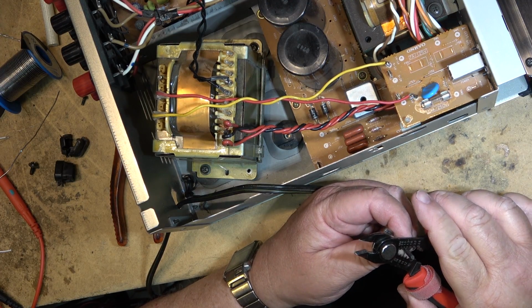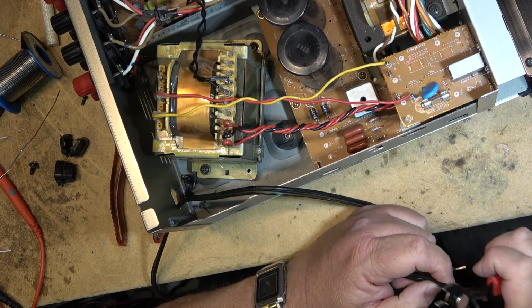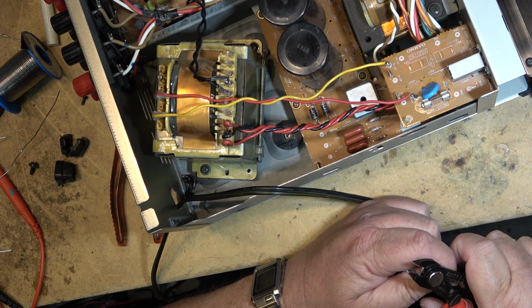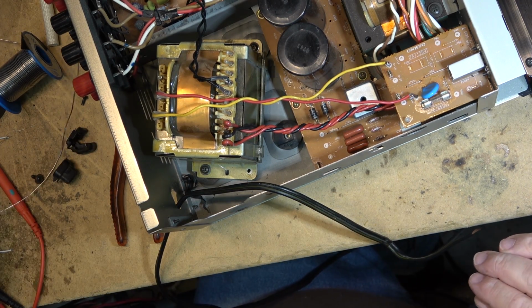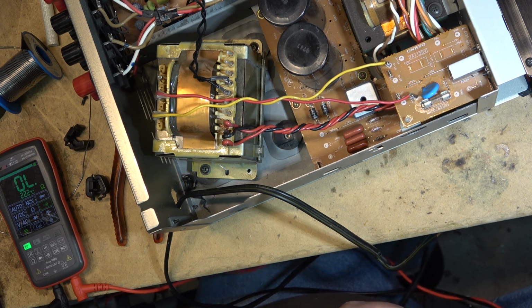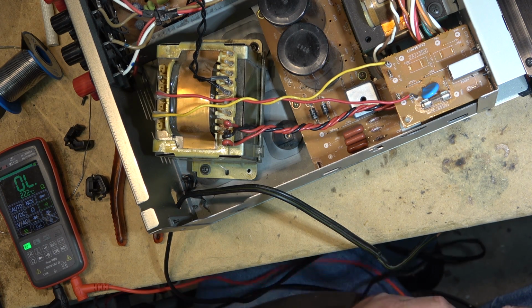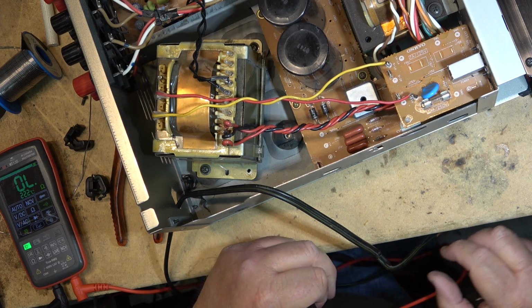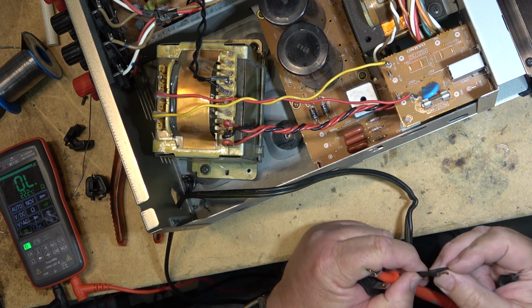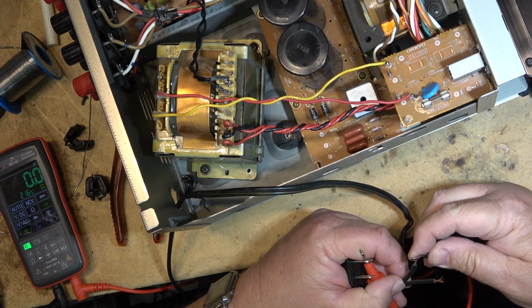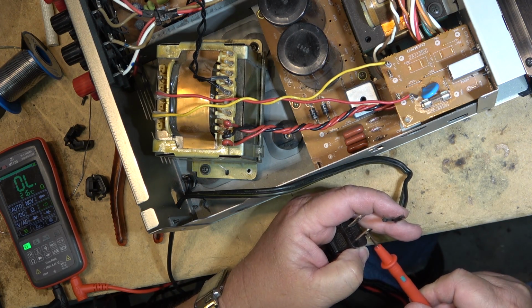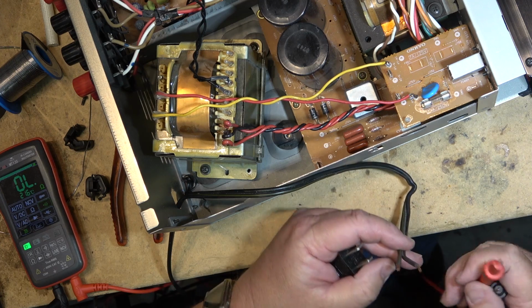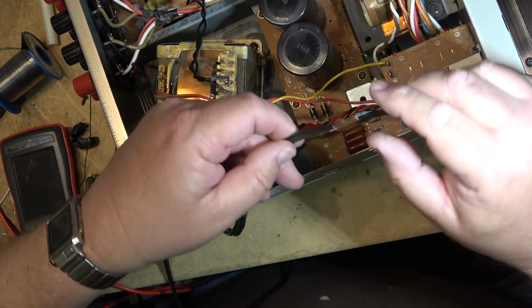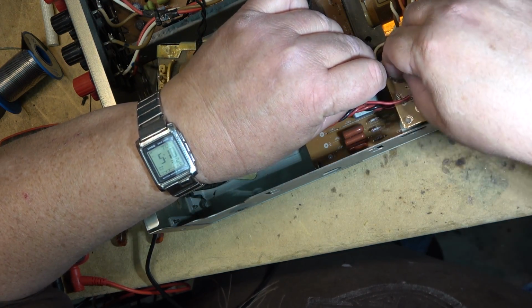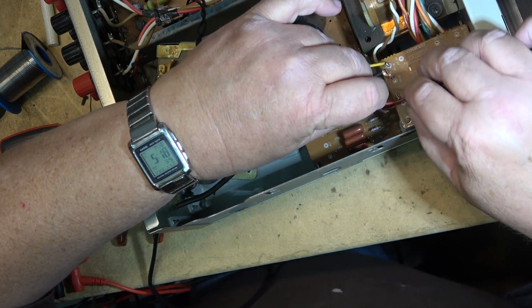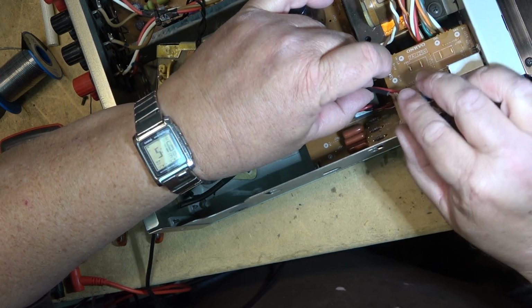Of course we have to make sure that the polarity is correct, so for that we can use the meter. It's a marked cord, it should be, the stripe should be on the neutral side. So the larger prong is the neutral, and that should be that one, which it is. And the hot side is the one without the yellow stripe. So the yellow stripe is going to go to the neutral side over here, and the one without the yellow stripe to the hot side.